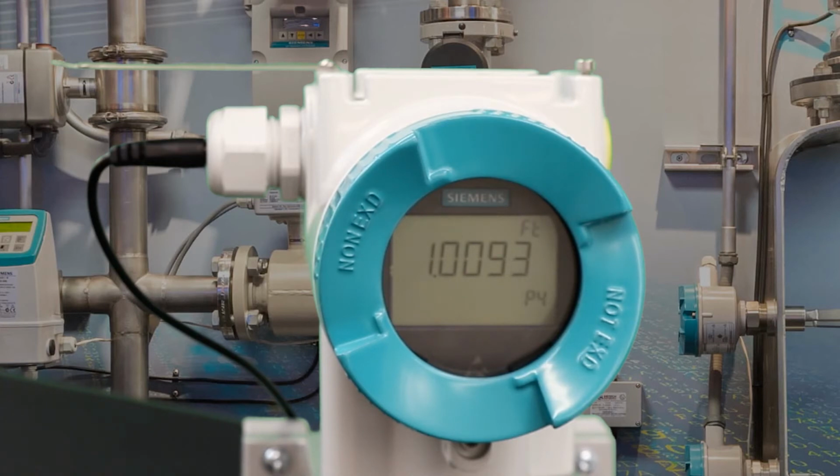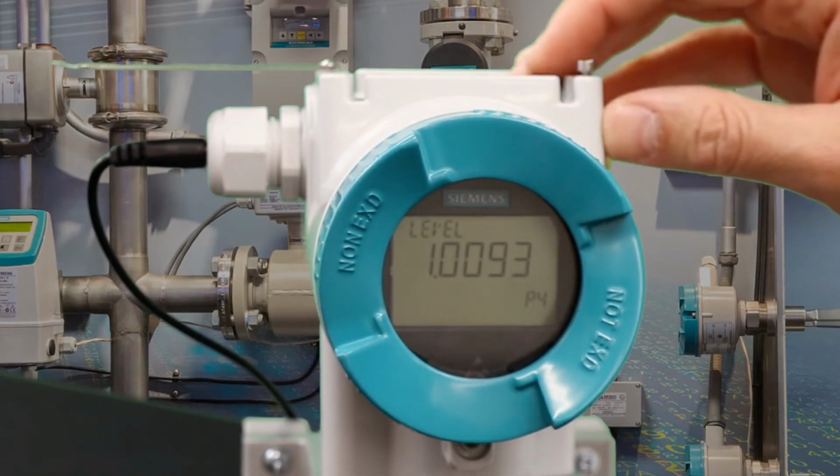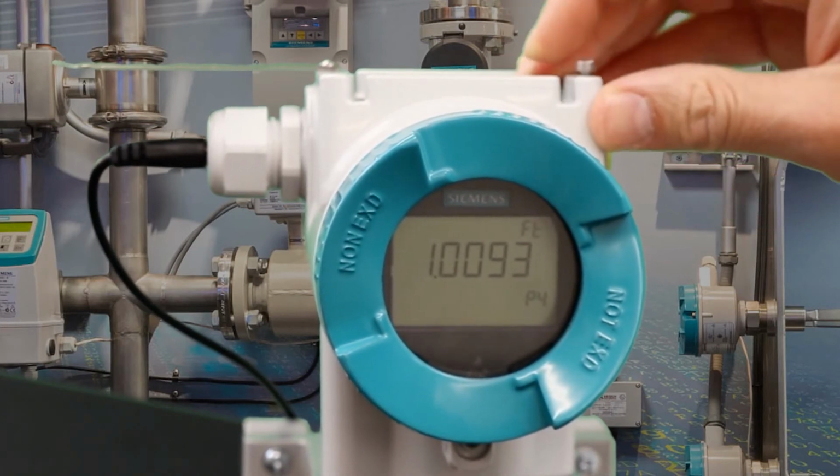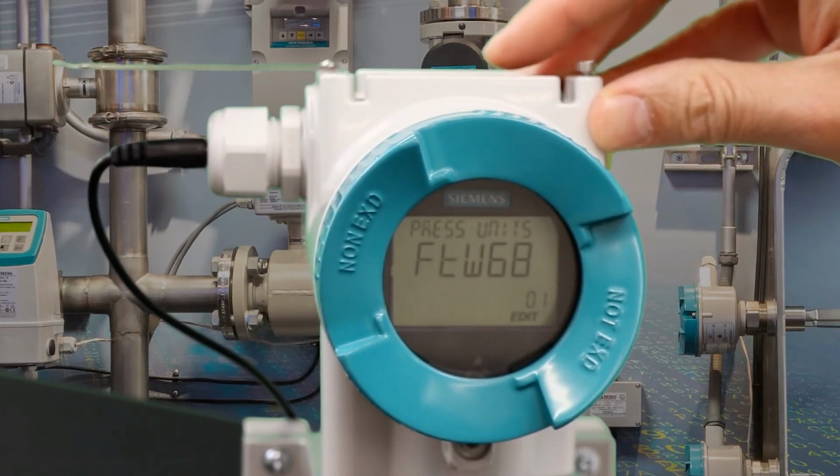Keep in mind, in this application, although the liquid has a specific gravity of 0.9, we went back one more time to assume that the pressure transmitter is mounted exactly at the bottom of the tank. So in this application, no need to offset the 1 foot or any level. All right, now we click on the right arrow. We go to the configuration menu.